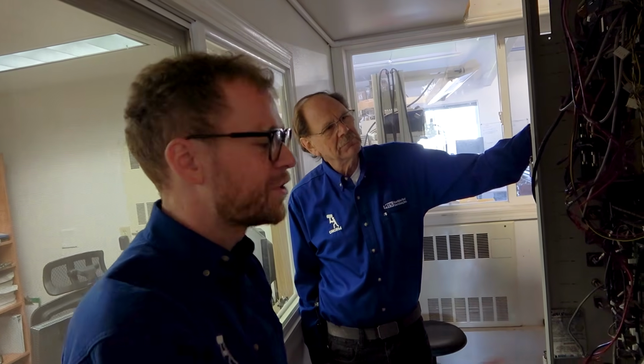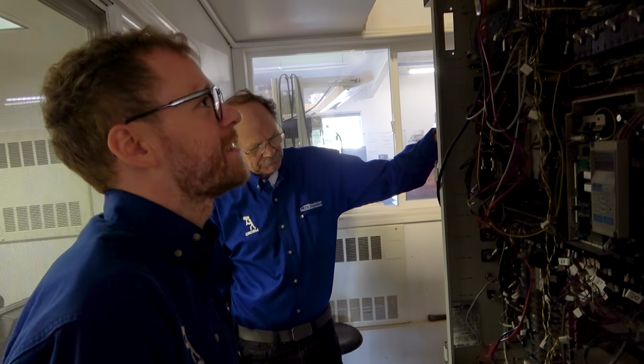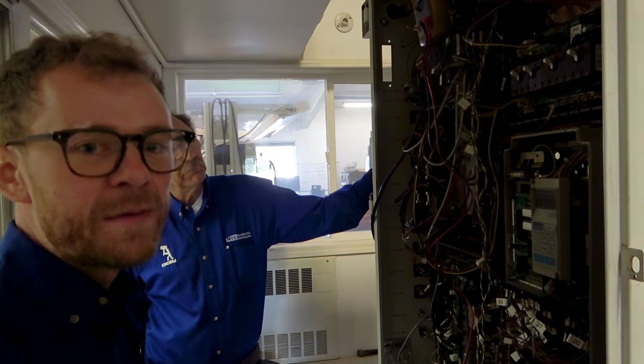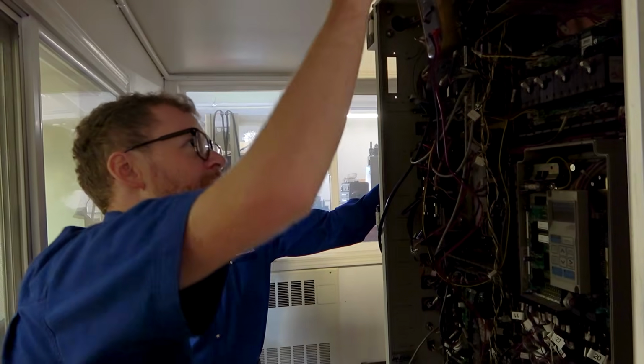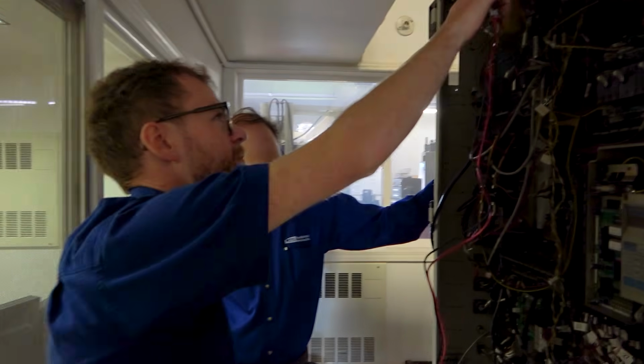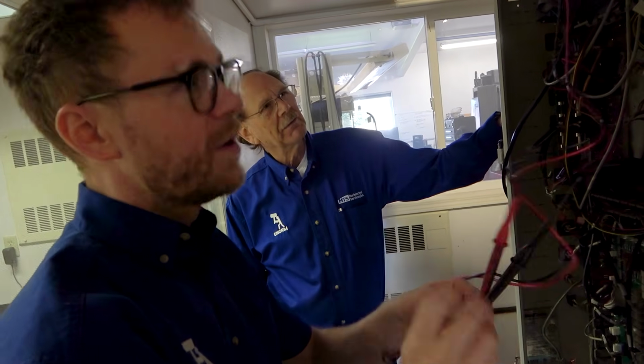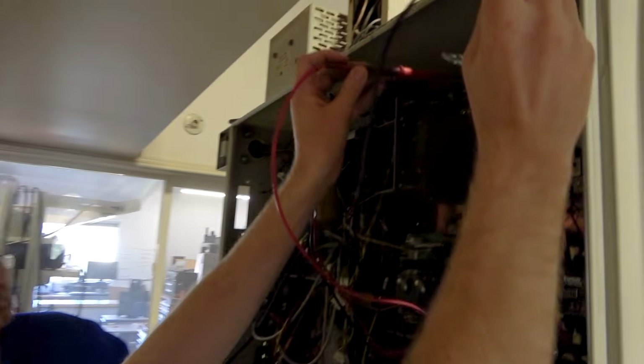So if your machine won't turn on, the most obvious and most simple check is whether you have good incoming power. Right, so let's start at the top of your breaker. Let's put your voltmeter in AC mode, and we're going to check the 3 incoming lines at the top of the breaker.